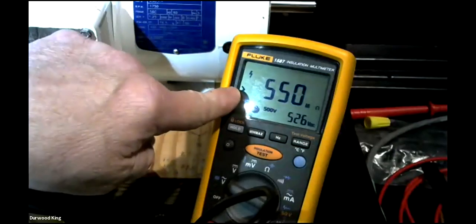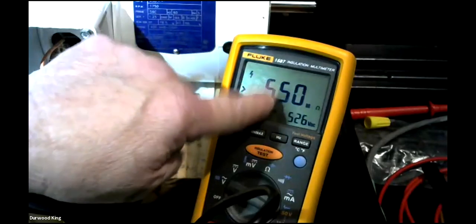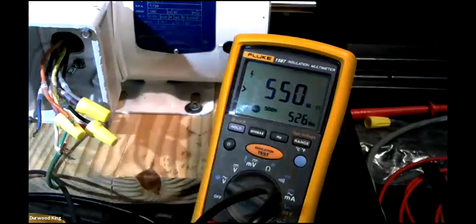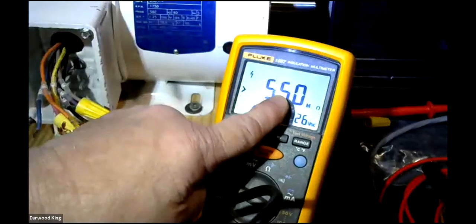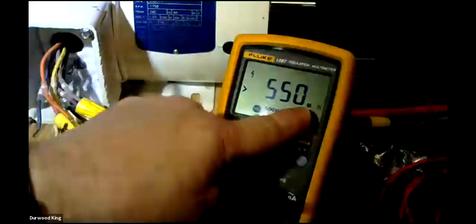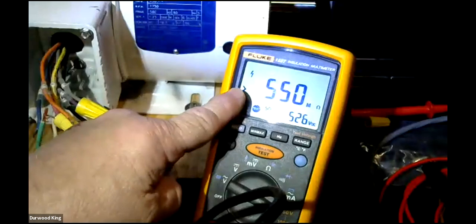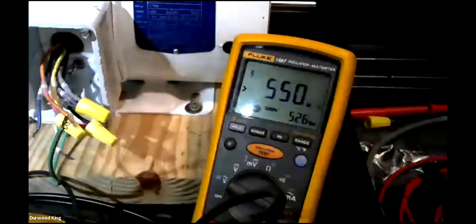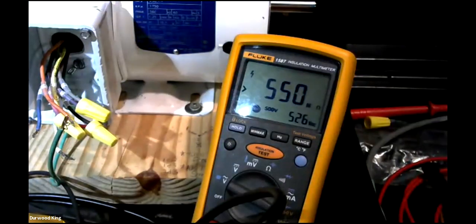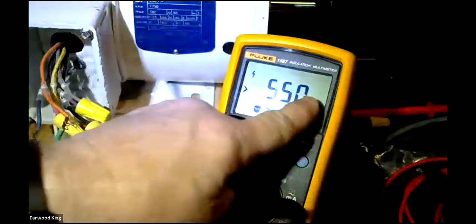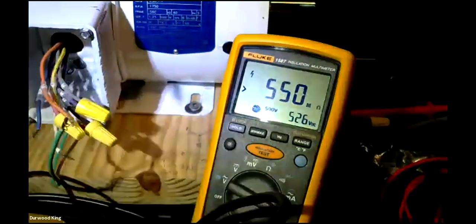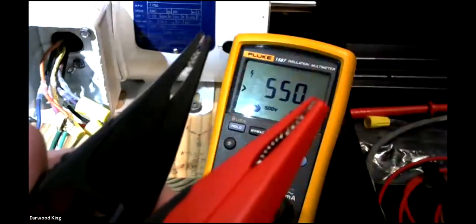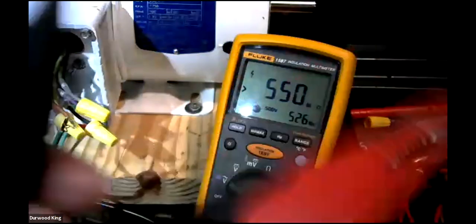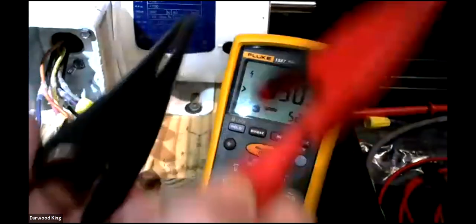Greater than 550 million ohms. Greater than means it's actually above what the meter can read, no higher than that. That's the maximum resistance. It can read 550 meg on this meter. Greater than means it's actually above that, which is effectively an open circuit, okay? It doesn't say OL, it just says greater than the highest reading it can do. Now that's with it open, that's what it's supposed to be. It's supposed to be so high that it's beyond what it can read. And then I let go, of course, it holds it on there.